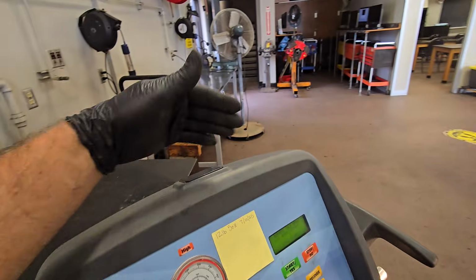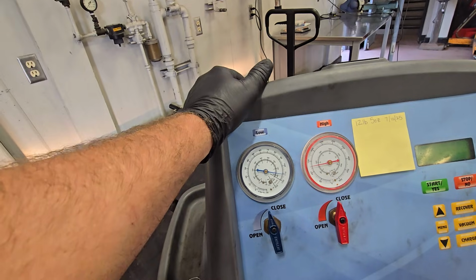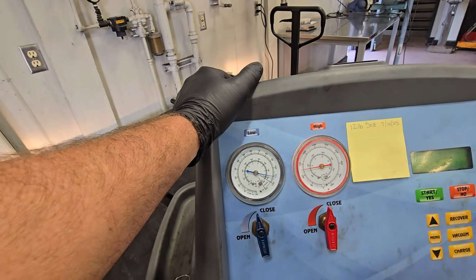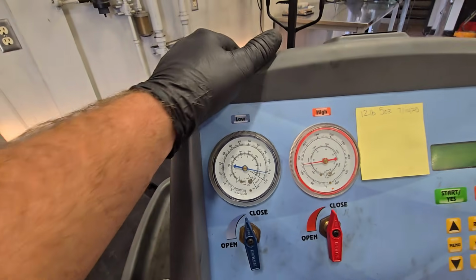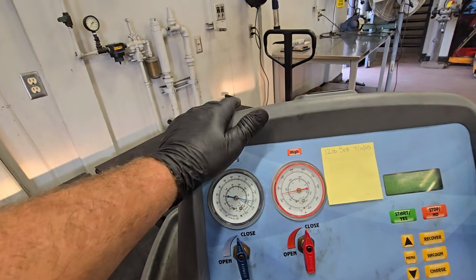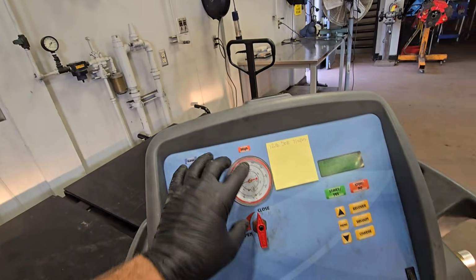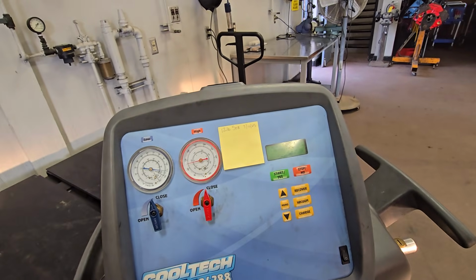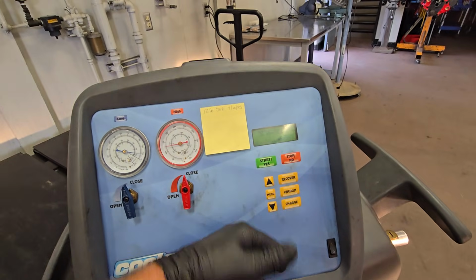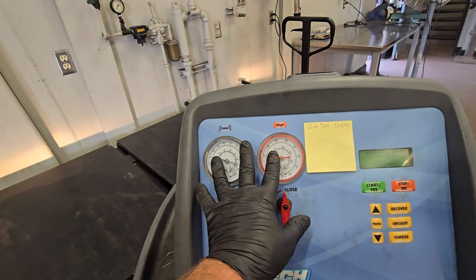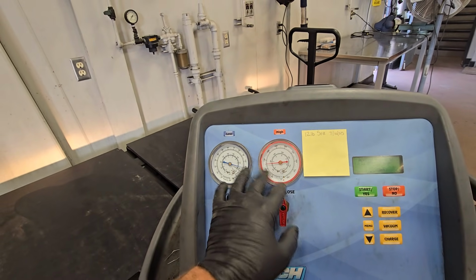I'm going to call it, it's probably about 90 in here right now. So we should have about 100, maybe 105, maybe even as much as 110 PSI if the system is charged. I just verified the system is charged. I didn't do what most brainless techs do and recover the system to see how much is in it - I already know how much is in it based on these static pressures, cool?